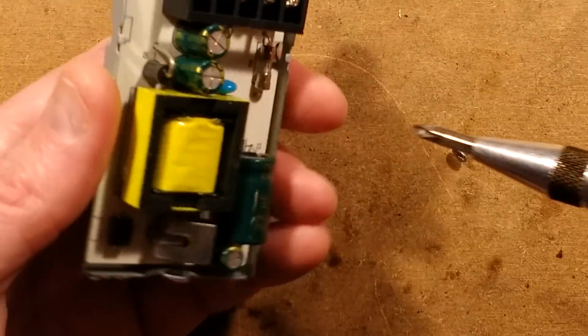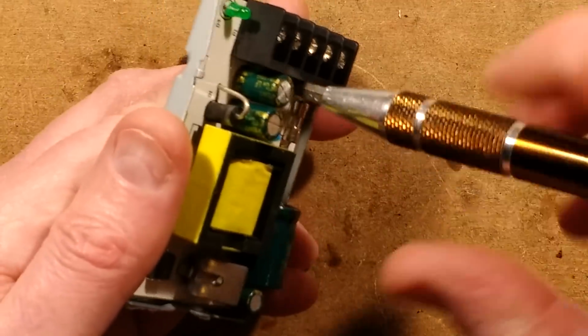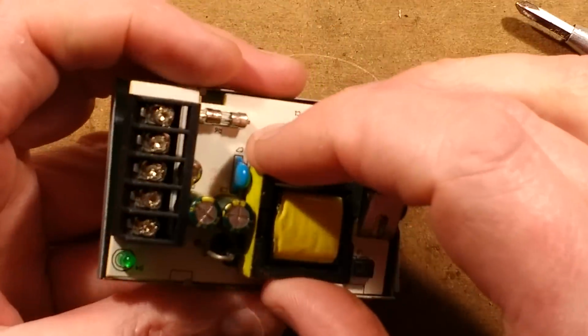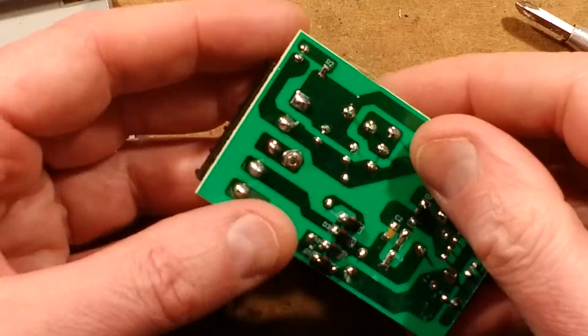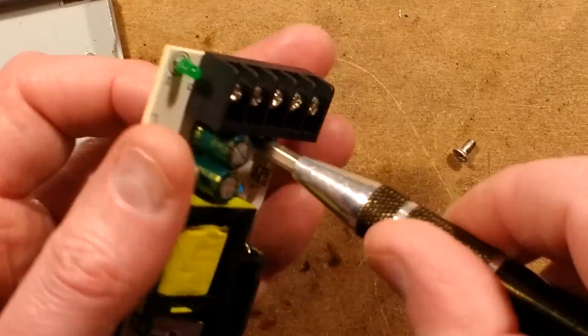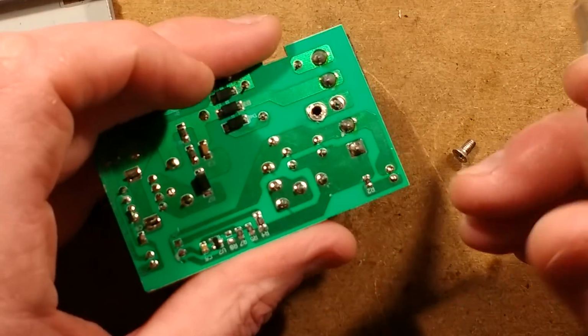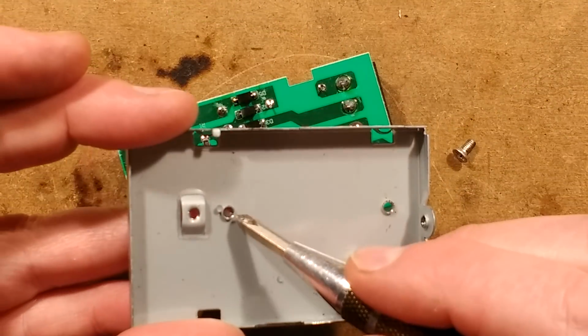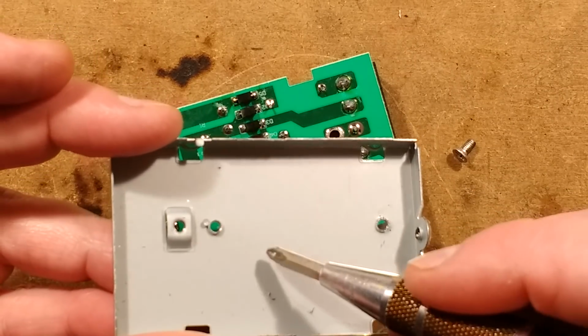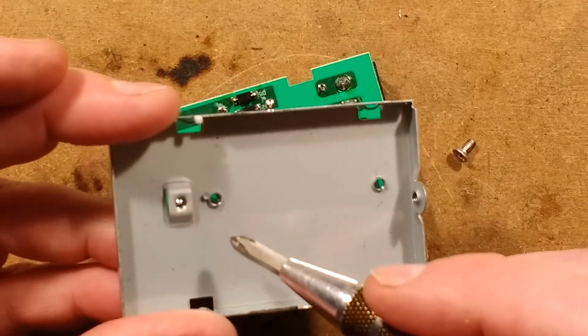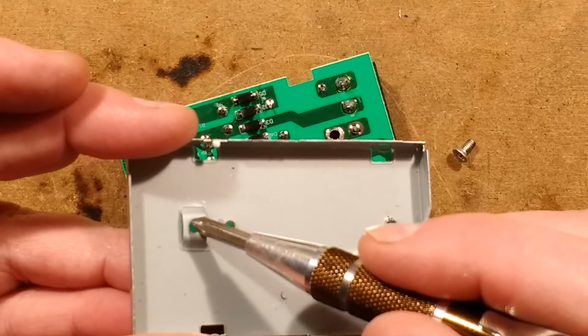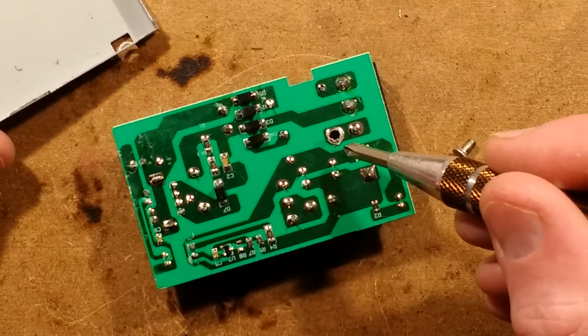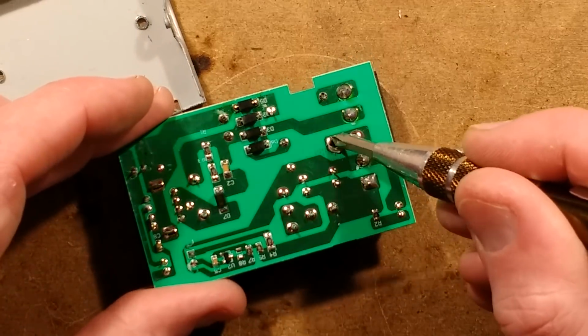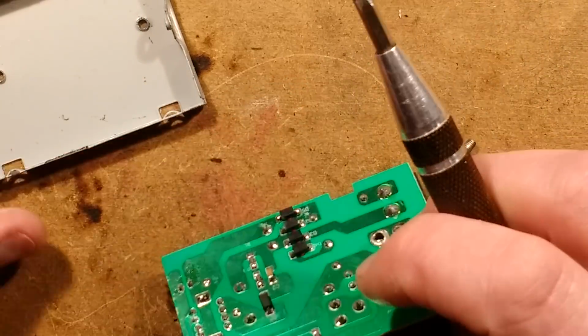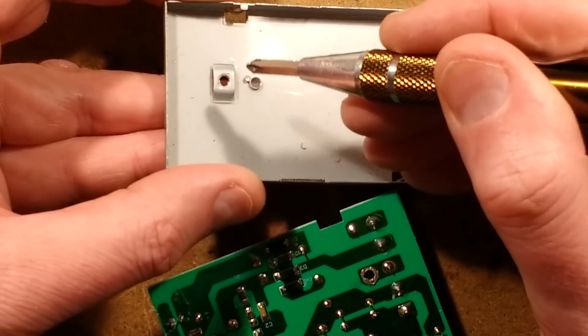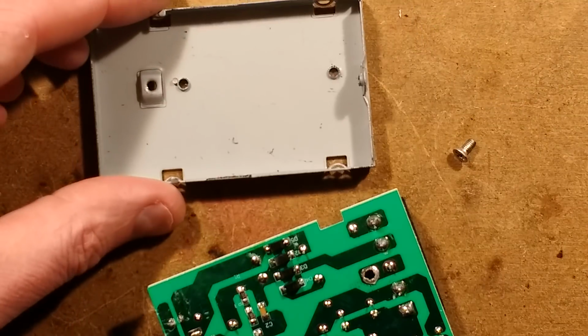How does this come out now? We've got a screw here. So the tests I've already done are high voltage tests. First I connected live and neutral, I bridged them together. I'm quite liking the earth connection here - it's onto this punched hole, one of the fixing holes, onto this raised surface. It's got a fairly big bit of solder here, although that just goes onto a sort of anodized surface. Is that conductive?